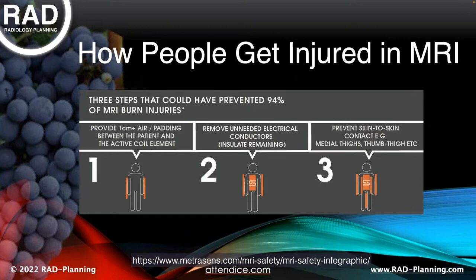And there are multiple accounts of patients who come out from MR scanners and say, I got this itchy spot on my elbow or my shoulder, or typically something radially positioned that would have been up against the wall of the bore of the magnet. And over time, outside of the magnet, you'll be able to watch a burn develop superficially. The burn actually already occurred, but it occurred in the subdermal fat layer, and now it's just propagating up. Essentially, that heat is causing tissue death in the subdermal fat, and it's migrating its way out to the dermal layers.